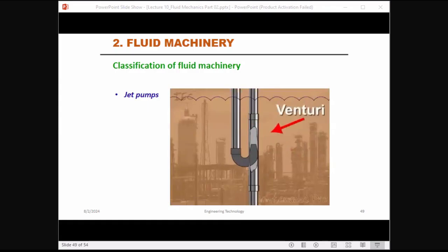As the water enters the nozzle, it is forced through the venturi. This creates a vacuum which draws the water up from the well through a foot valve. As the water passes through the venturi tube into the suction line, the pressure is increased sufficiently to force the water back into the pump impeller.